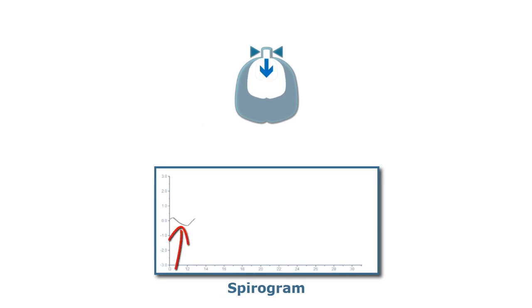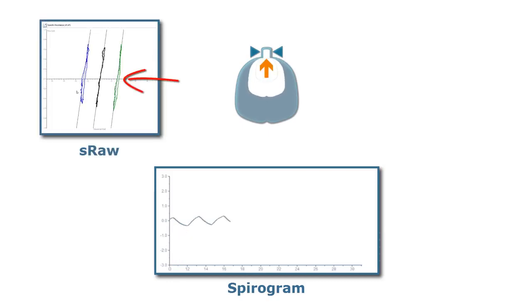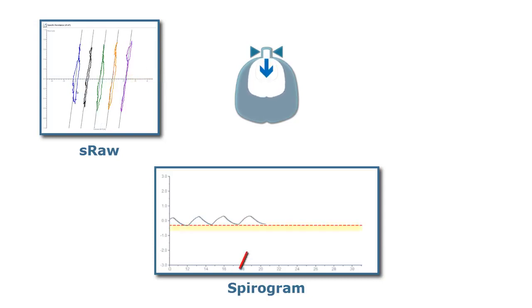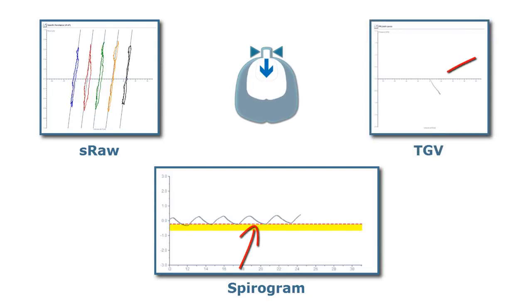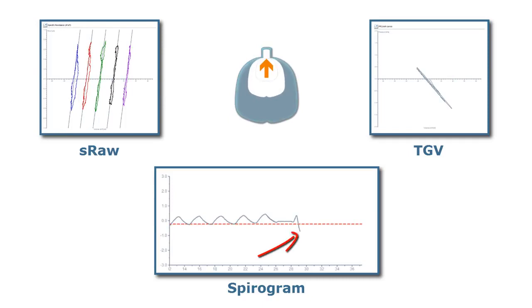The measurement starts with quiet breathing. During this phase, specific airway resistance is measured. After a stable breathing level is achieved, a shutter will be closed to determine thoracic gas volume. As soon as the shutter opens, a vital capacity is performed in order to calculate the absolute lung volumes.